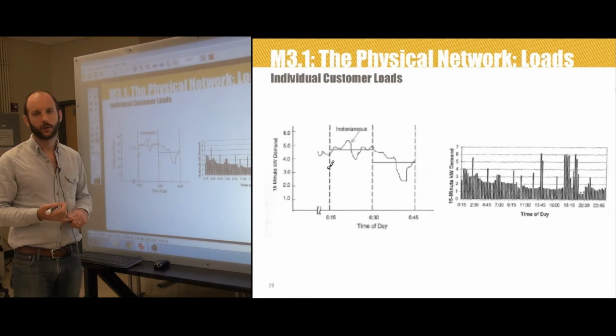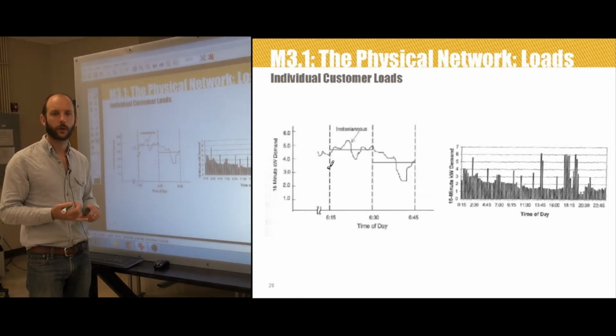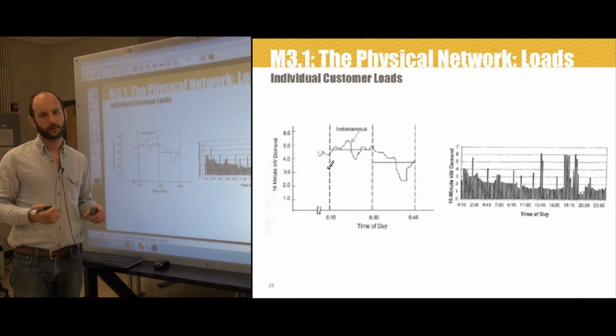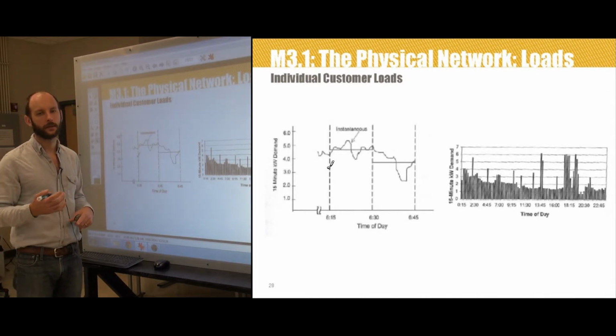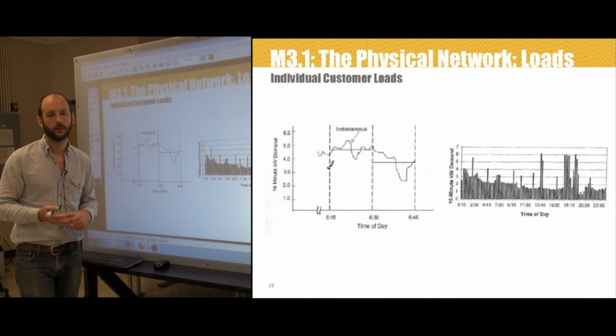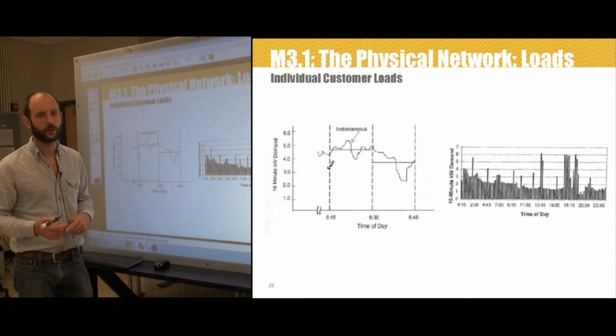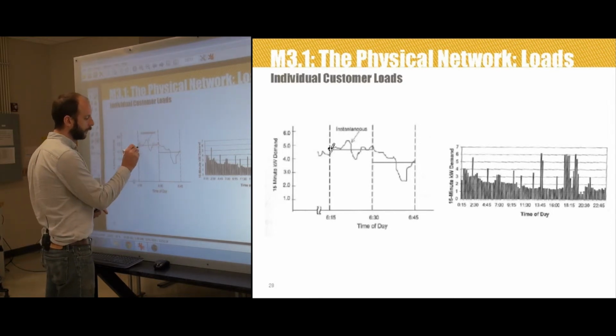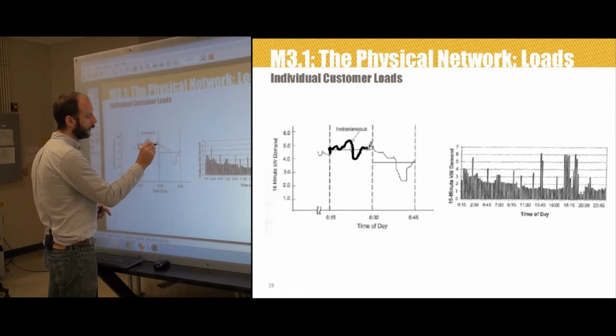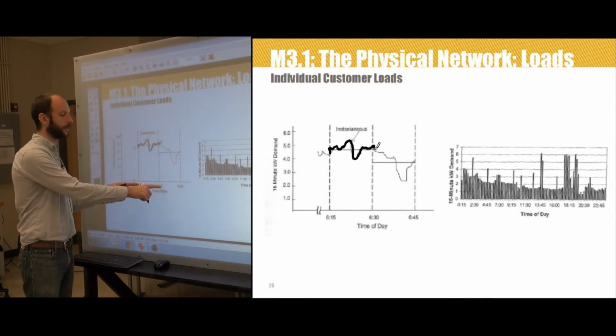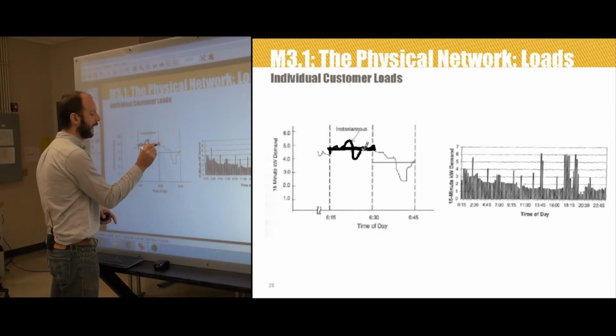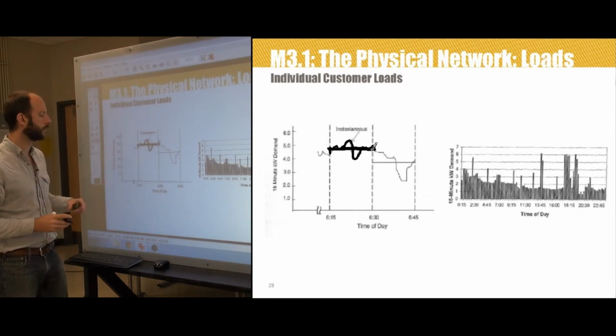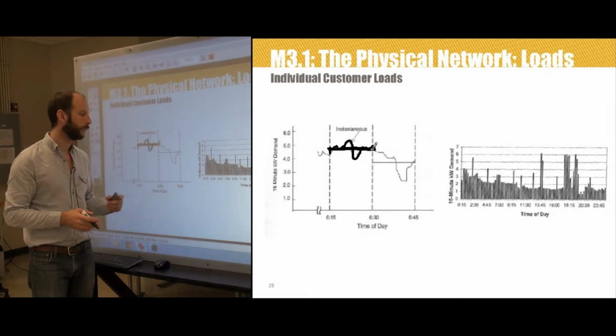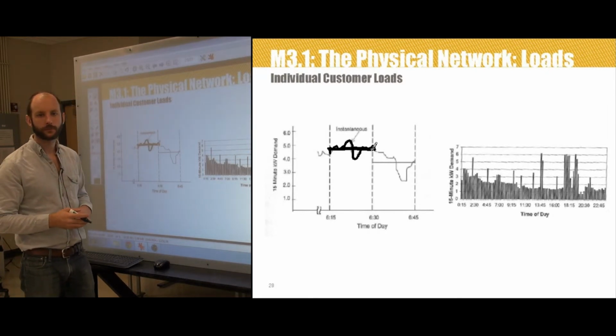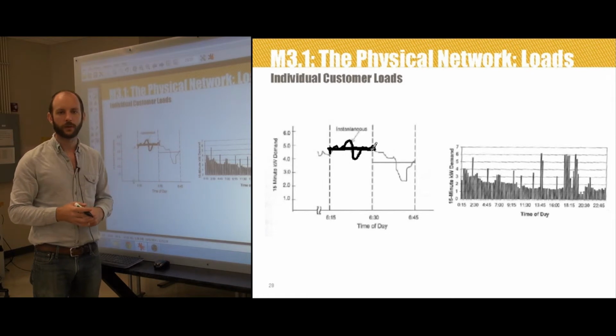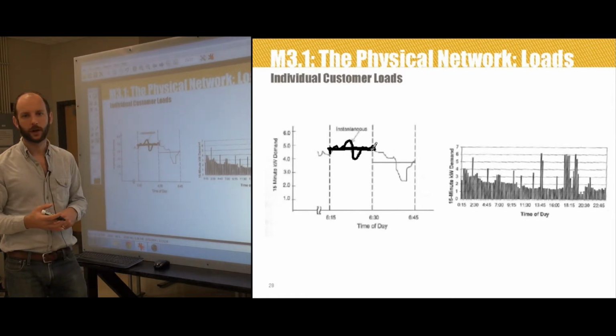To define this load, the demand curve is broken into equal time intervals, and a customary interval in the electric utility industry has been historically about 15 minutes. In each interval, the average value of the demand is determined. So for a 15-minute interval, I will integrate the energy, I'll divide by the time interval, and what that gives me is this average value of demand in kilowatts or megawatts or what have you. This straight line then represents the average load during that 15-minute time interval.